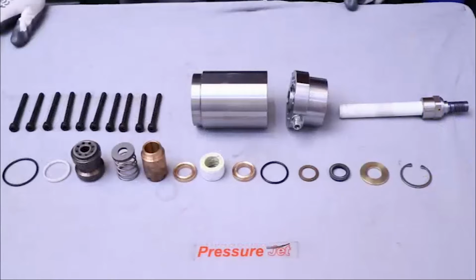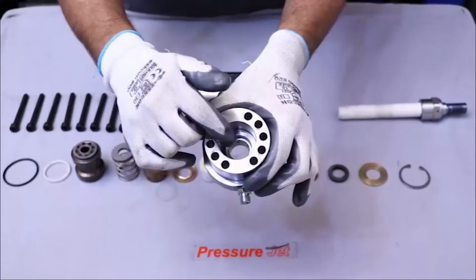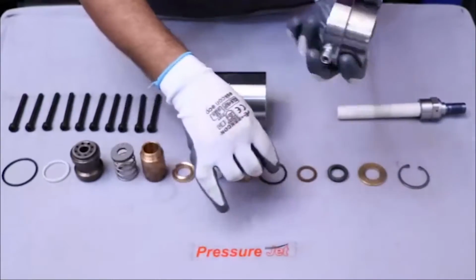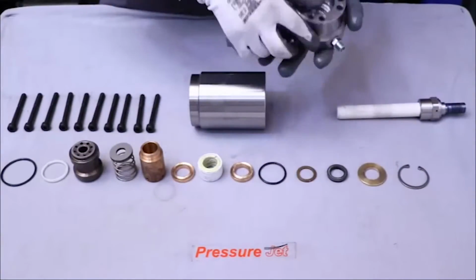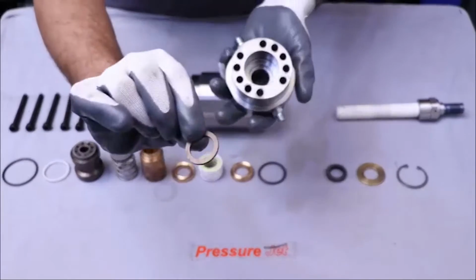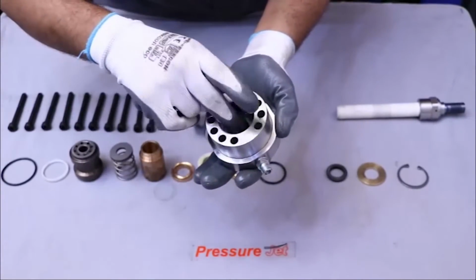It is a standard practice to replace some wear and tear parts at intervals to prevent breakdown. Check the life of those parts from the preventive maintenance chart. Now start stuffing box assembly. Firstly, take the stuffing box cover. Assemble the low pressure seal gasket inside the stuffing box cover.